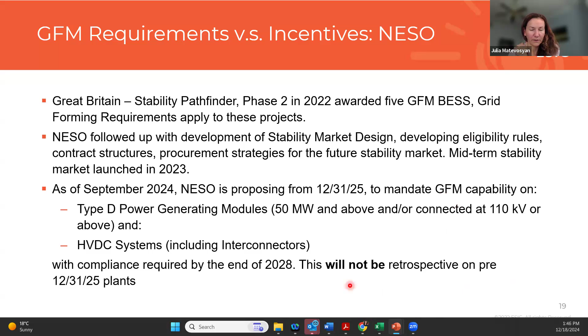National Grid followed with development of a stability market design and developed eligibility rules and procurement approach, and the midterm stability market launched in 2023. But as I mentioned, in September this year, National Grid started looking at potentially requiring grid forming capability from the largest type of generating modules—50 megawatts and up, connected at 110 kV and up—for all of them to be grid forming. This also includes HVDC systems, including interconnectors. If this requirement goes into force, compliance will be required from 2028, but it will not be retroactive to existing resources.